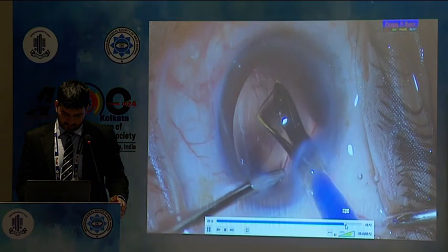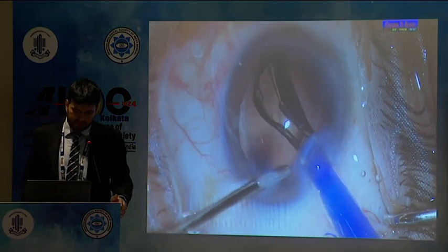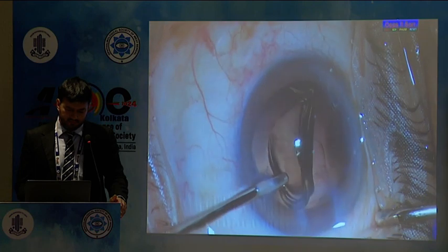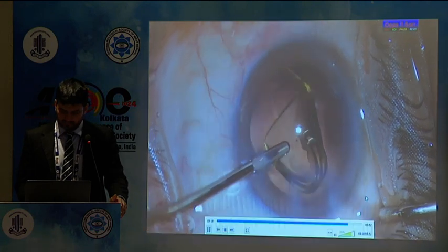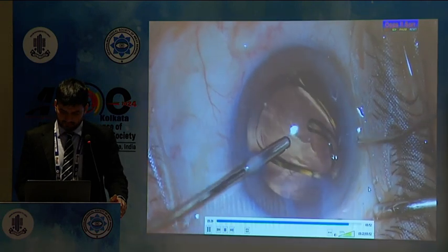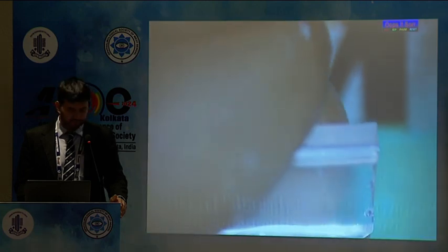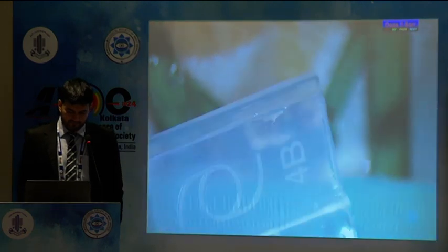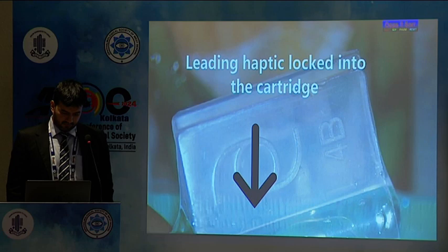Later on, I watched the recording and saw that the leading haptic was broken. I was eager to know where it actually happened. So I rewatched the recording carefully and saw that while loading the IOL in the cartridge, the leading haptic got stuck in the cartridge while locking it. And this was the reason for the broken haptic.